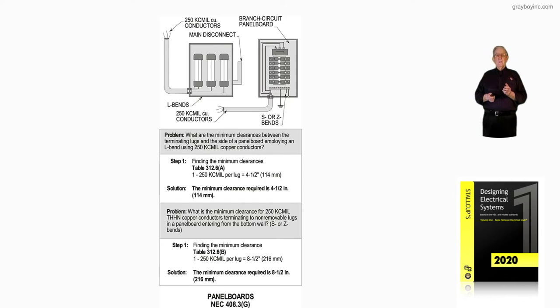The table that is used for the L-bend is Table 312.6A, and notice with that 250 kcmil coming in with an L-bend, it's four and a half inches from the L-bend lug to the bottom of that enclosure. The industry calls that an L-bend, which you can read about in 408.3G in the text.